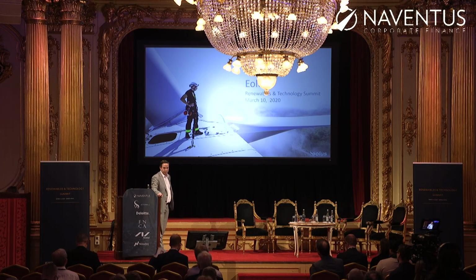But this is an old picture. This is from a turbine and wind farm we built back in 2015. It's a Vestas V112 model. And the number, when you speak about wind turbine models, is the rotor diameter, 112 meters diameter of the circle that the blades sweep over. So meaning that the blades are 56 meters long, and then the tip height is 150 meters in this case. This would be hopelessly outdated to build in Sweden today.